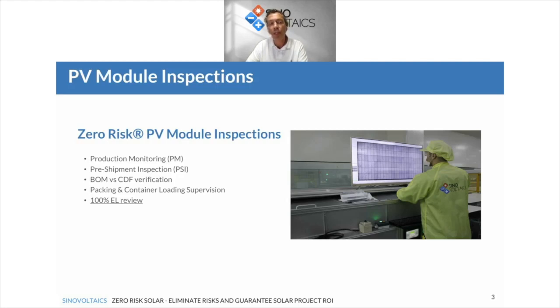Then there's the bill of material check, which is a quite important check to verify that the manufacturer is actually sticking to the certified BOM. They're not allowed to use materials that have never been tested in that material combination before. Otherwise, you're practically buying an uncertified product. So we're strict on that. We inspect that. It's about 1 out of 6 inspections we see deviations in that. So it's something to keep a close look on.